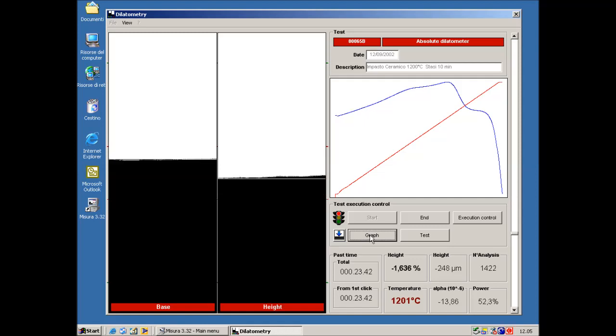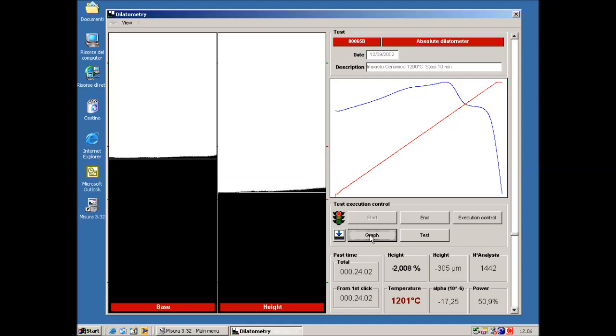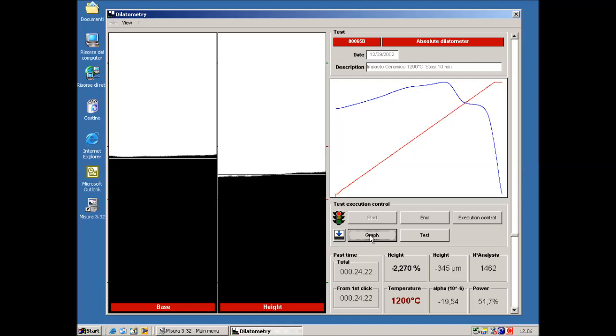The thermal treatment set for this test is made of 3 steps: heating up to 1200 degrees centigrade at 50 degrees per minute, holding the temperature of 1200 degrees C for a period of 10 minutes, and then cooling. The material is sintering very fast, and the step motor is working quite often to bring back the image in the center of the window. The interval at constant temperature starts when the temperature reaches 1200 degrees C. Note that the temperature of the kiln overcomes the set point by only 1 degree.